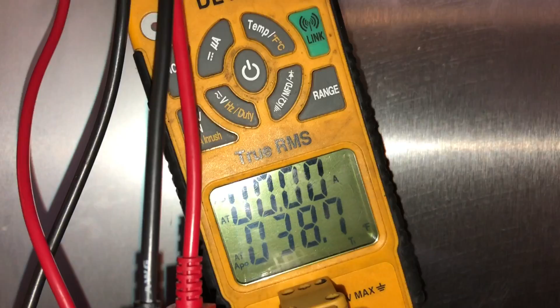I'll show you guys. Come over here to the customer settings. 0. A1. And I'll go up to EL, should be our evaporator sensor. That's our evaporator sensor. So I got a 31 degree evaporator. And then CB is our cabinet sensor. It's reading 71.5. We're at 38.7.